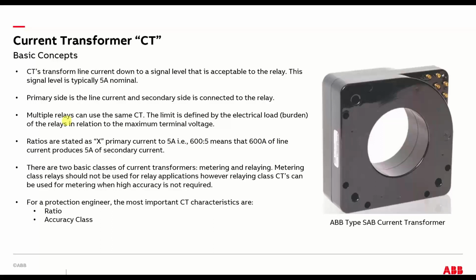The limit is defined by how much physical load that CT can drive, and that is relative to the accuracy class of the CT, and that gets a little complicated. But the larger that class is, and it's usually like a C something, like C100 or C200 or C50, that C accuracy class basically is equivalent to how much electrical load the CT can drive and remain accurate, remain out of saturation. And it's sort of like terminal voltage.